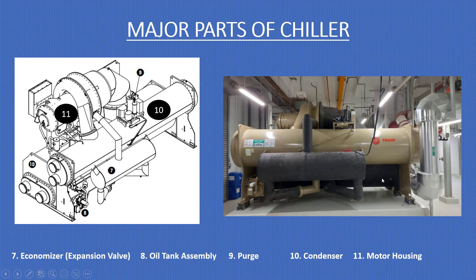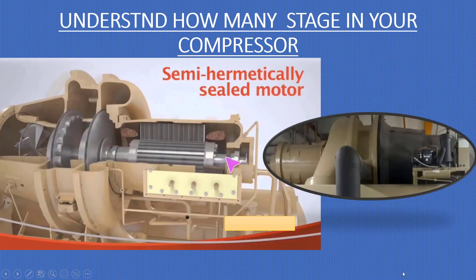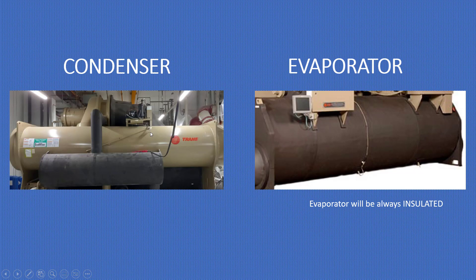Some other major parts you can see here include the economizer, oil tank assembly, condenser, and motor housing. We have taken both manual pictures and site photos so you can compare them. Understand how many stages are in your compressor. This is a semi-hermetically sealed motor with a two-stage compressor. Refer to your manual to identify what type of condenser and evaporator you have. The evaporator will always be insulated to avoid heat ingress.